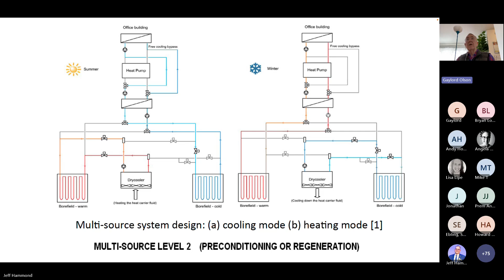If you notice on the left-hand block diagram, this is the summer case — they're not even using the heat pump and compressor, they're bypassing it in economizer mode. That's a very efficient way to get cooling. If you can do it, you need temperatures in the range of about 35 to 45 or 50 Fahrenheit, and then you don't need to use the electricity going to a compressor.